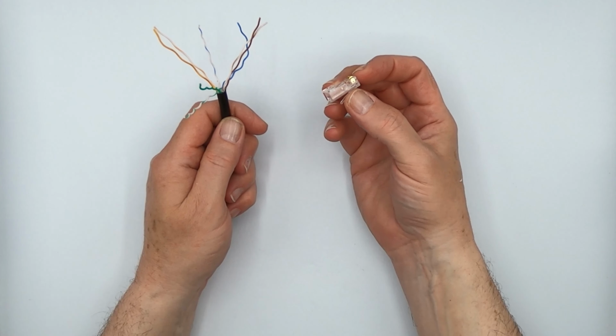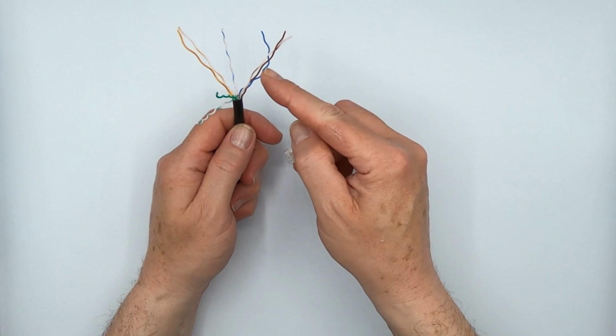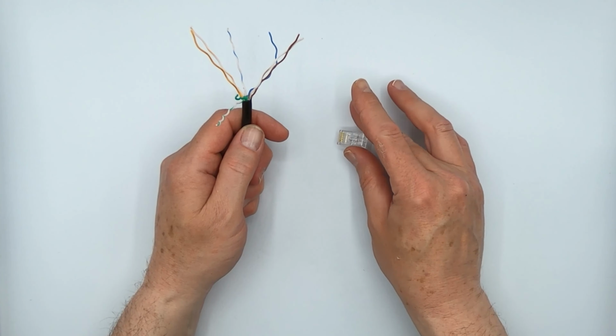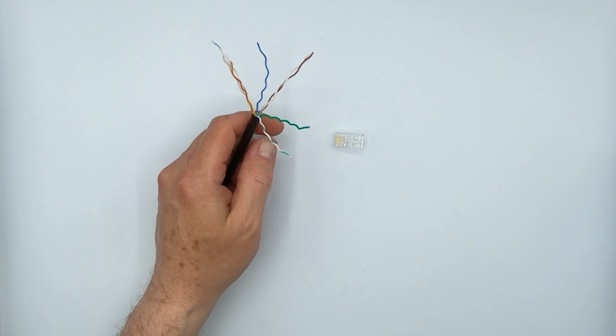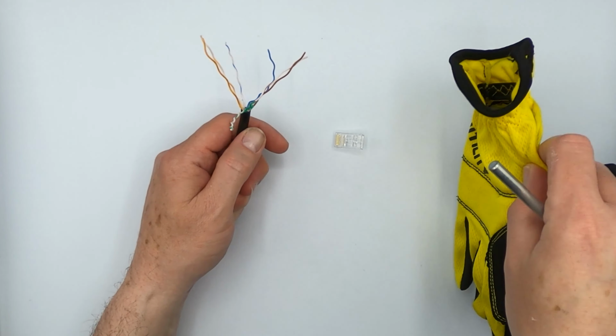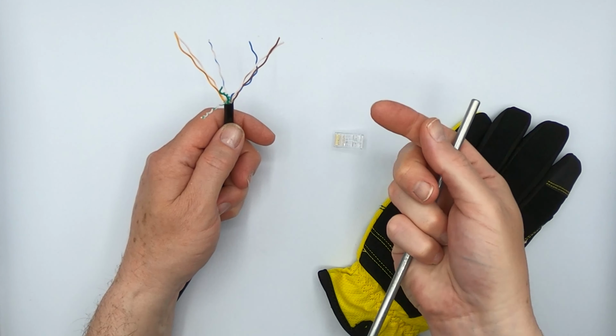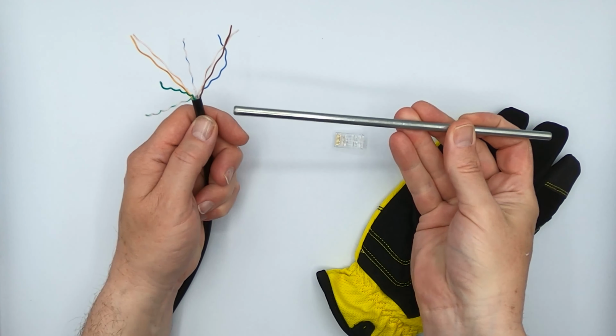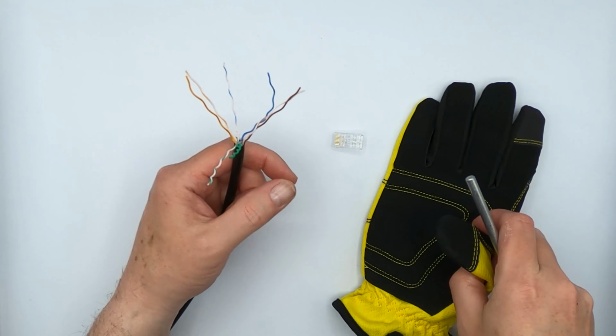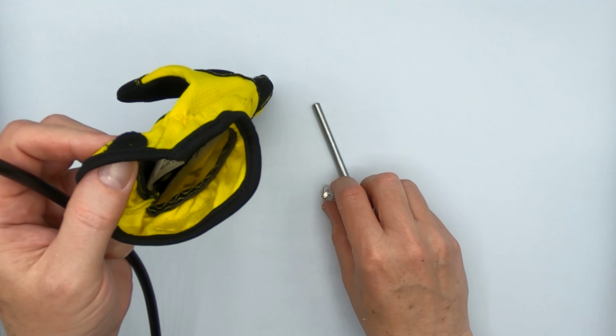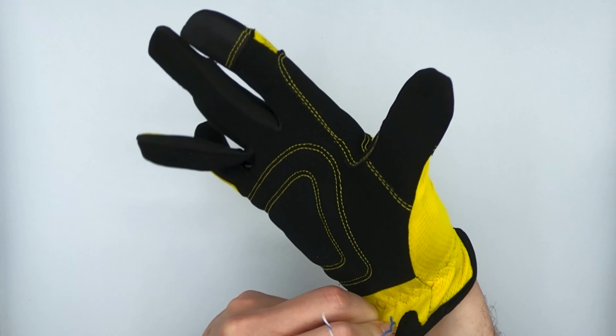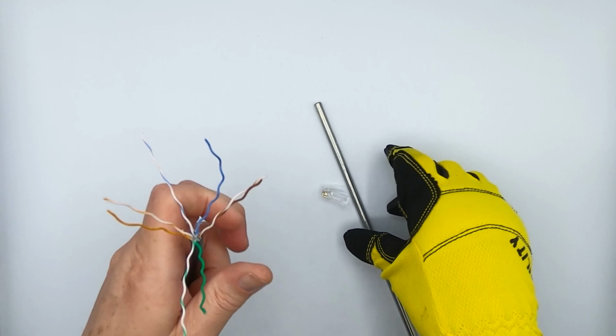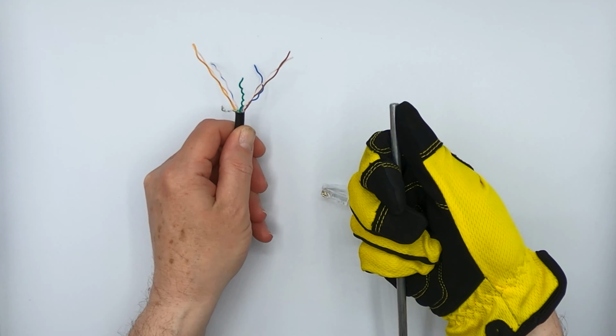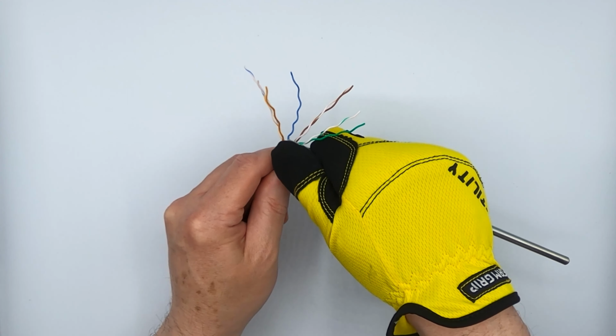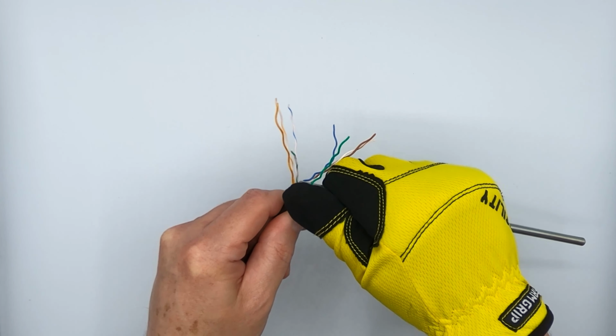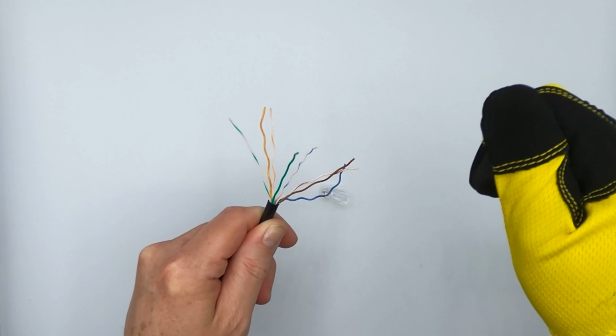And then we'll use our Category 6 pass-through plug, which has been fitment tested and performance tested with this cable. And the first thing you need to do, though, is comb out these conductors. So the quickest way to do that, and the least painful for your thumb, is to use a thin metal dowel like this, or a screwdriver shaft is a good substitute, and a glove. And then run the conductor between the rod and your thumb. Start at the cable jacket, work your way up. Only one or two passes is basically all you need to do.